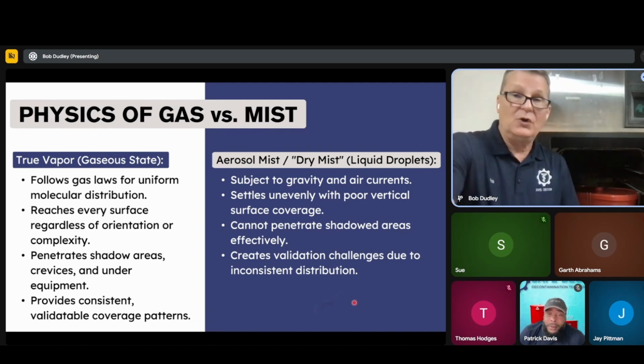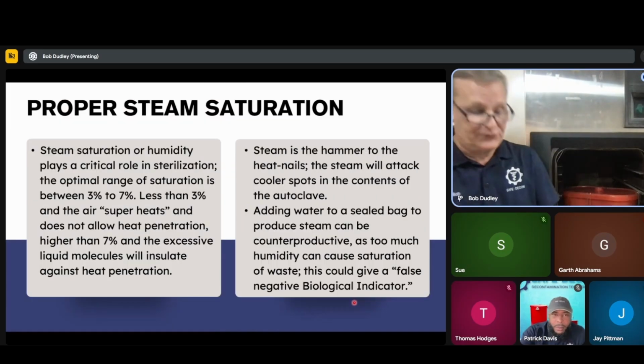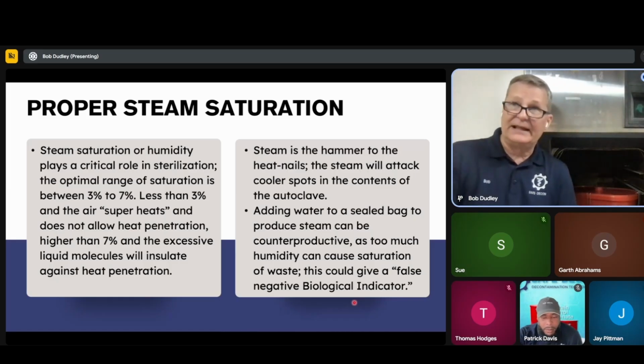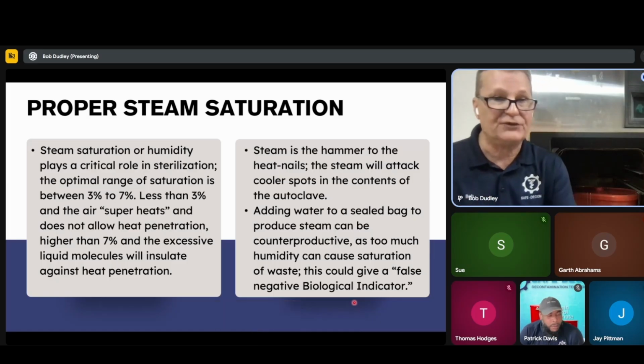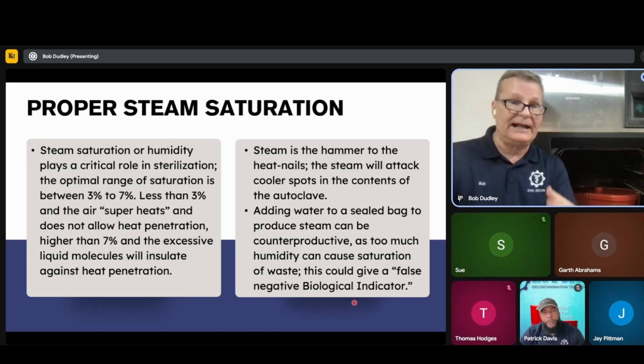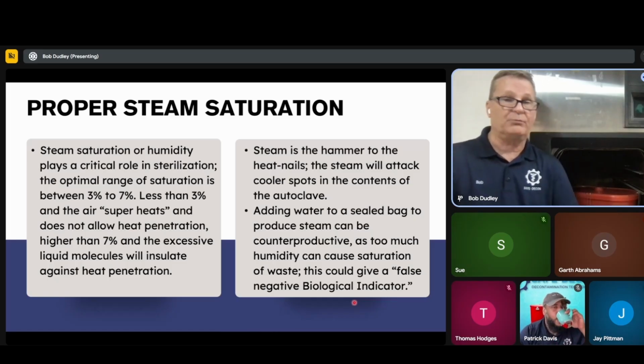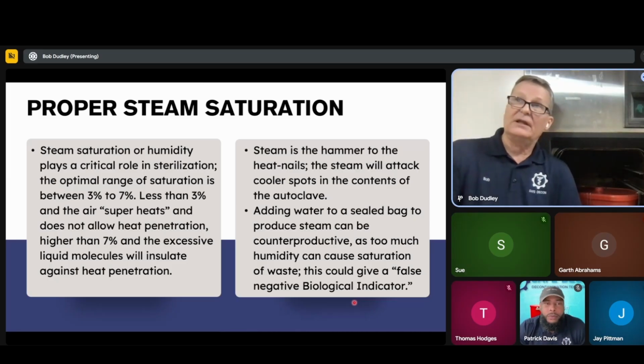And so with that and the difference between a gaseous state and mist, I want to get into proper steam saturation. And this is something that most people don't know. And it's what you don't know is what gets you in trouble. This is why I wanted to bring up the steam saturation, because it plays an incredibly critical role in decontamination sterilization. If your autoclave is working correctly, you will have a steam saturation or the humidity in that steam of between 3 and 7%. Let me explain the difference.